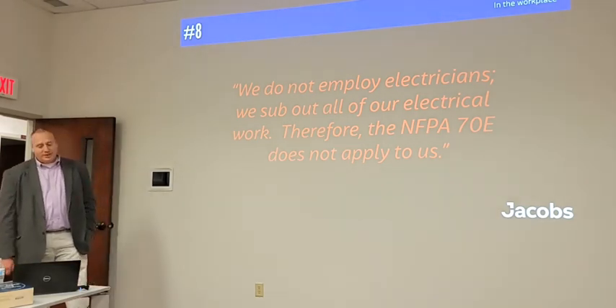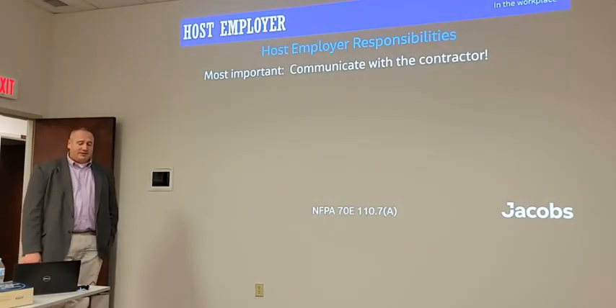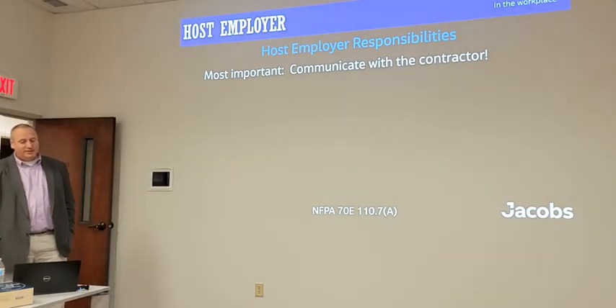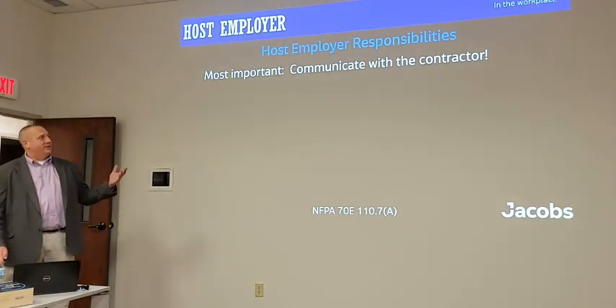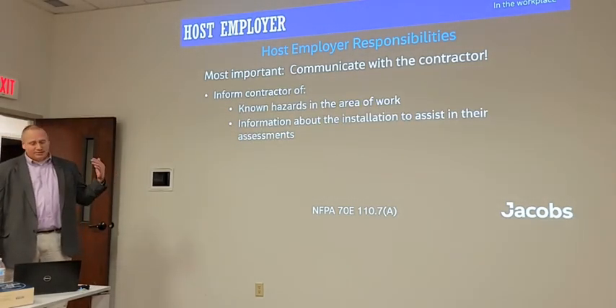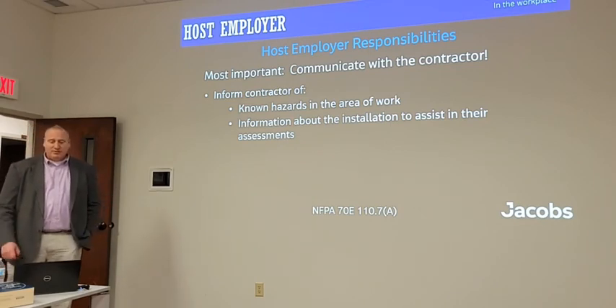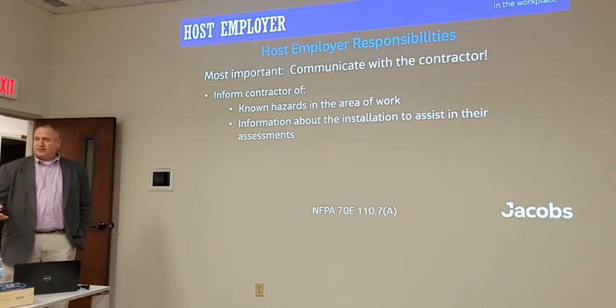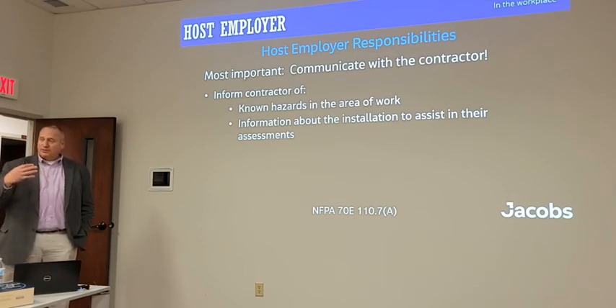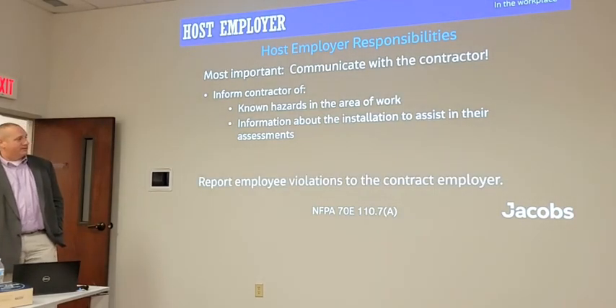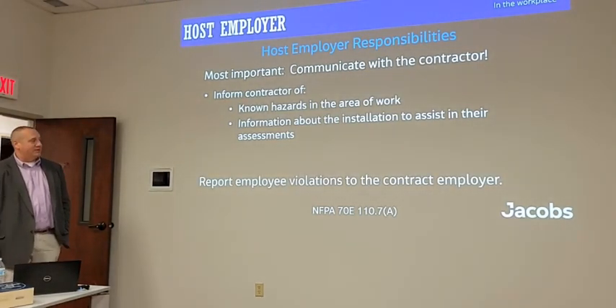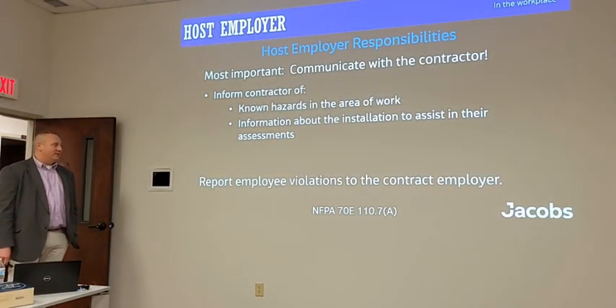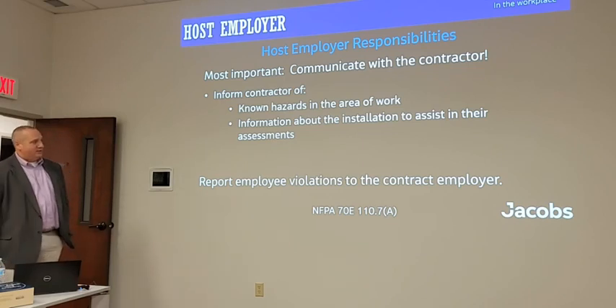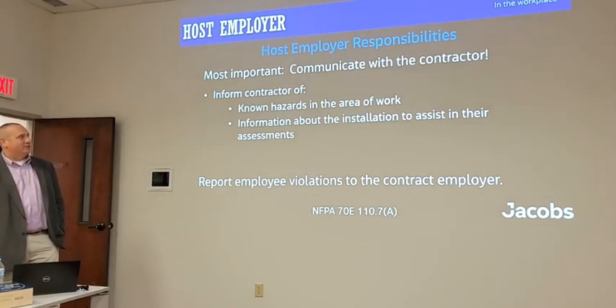Well, there are some simple things that you can point out for the 70E that are required for contractors or for employers. Whenever they have a contractor, they've got to communicate what the known hazards are, information that's going to assist them in their risk assessments, and also as the owner of the equipment, you're still responsible to provide the arc flash assessment to be able to determine what PPE the contractor is going to need, and then report any employee violations to the contract employer.